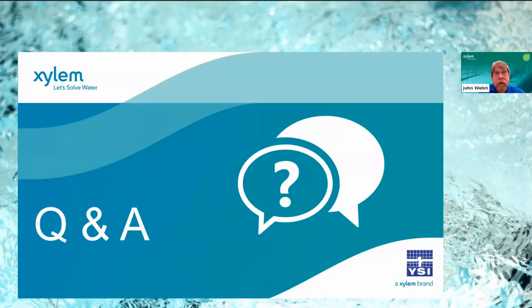So you have to have dedicated ports in order to do that. But in most cases, particularly in water treatment, you can get by with 4 sample points, 2 being the most commonly used. So direct to the question, practically everything on the 9220 was redesigned and improved from the 9210P.